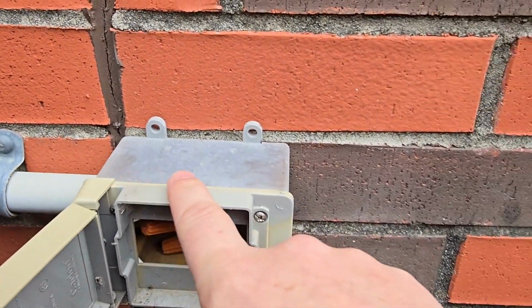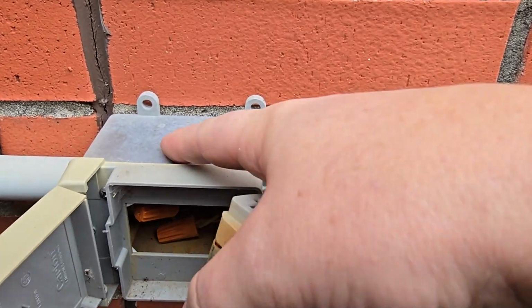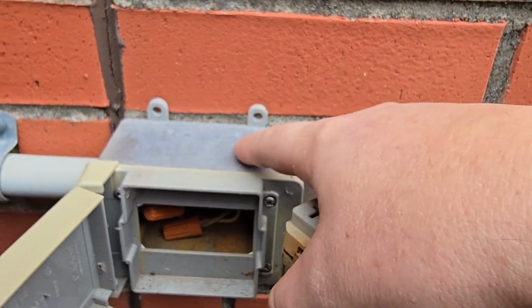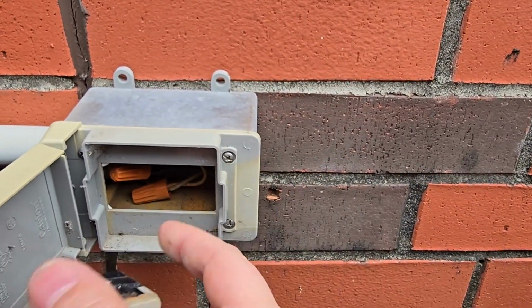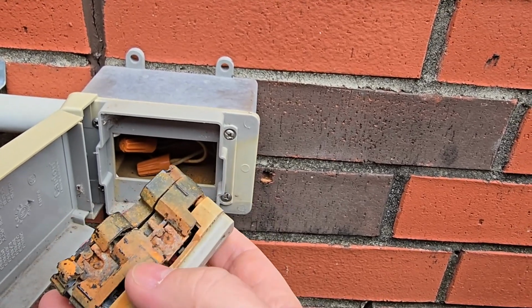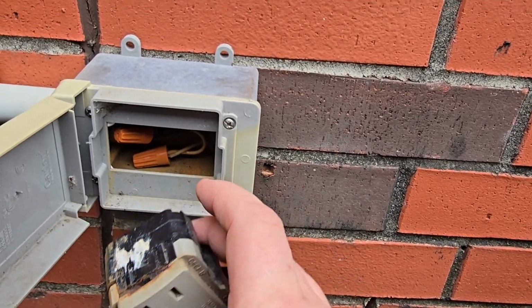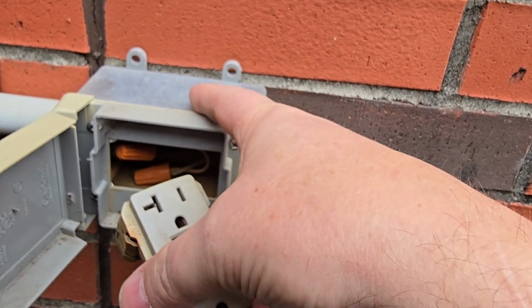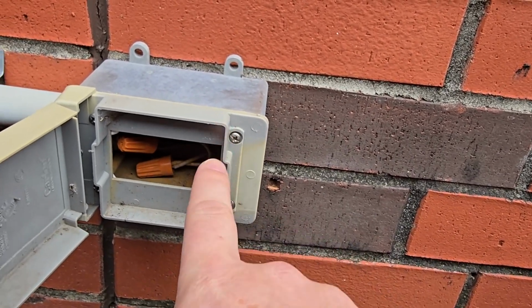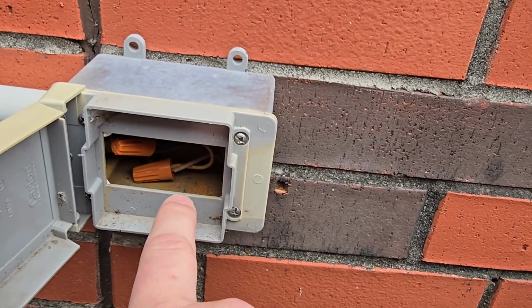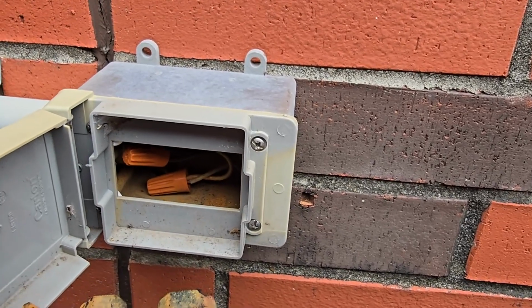So I removed the lid, and there's a divot right here in the plastic. I believe that's due to heat, because as these contacts got loose, they heated up the box, which created a divot, and that broke the seal and allowed water to probably fill this box completely.